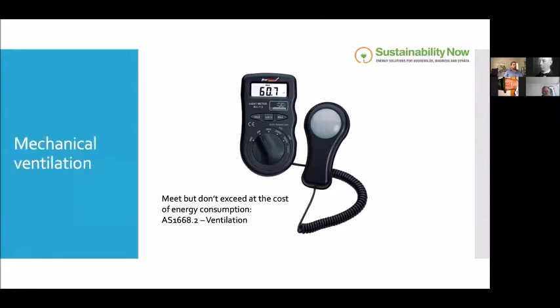Mechanical ventilation is another one - Australian Standard 1668.2 has a big list of requirements. For example, car park ventilation fans must run 24 hours a day, 7 days a week, unless you monitor air quality. That's why we like to install carbon monoxide sensors in the car park to control those fans so they only run the bare minimum necessary. Timers aren't compliant with the Australian standards because they're set at arbitrary times, and you could have adverse air quality outside of those times while the fans aren't running.